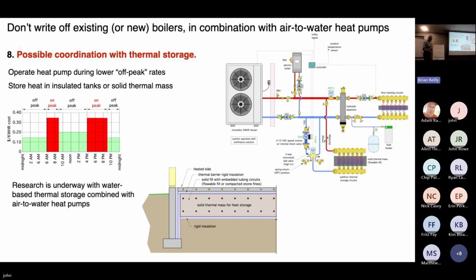People have asked me, can I just do a 12-inch thick concrete floor, put tubing in it, and charge it up on off-peak rate? You can do that, but you don't have control on how that heat is coming out. Suppose the sun starts coming through the windows, or you throw a party and you've got 50 people in your house. That's immediate internal heat gain, and you can't just stop that slab from releasing heat. But with some kind of a thermal barrier in between, you have some degree of control.